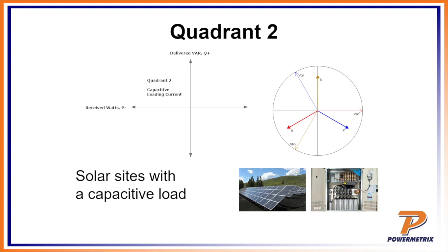So that power factor is going to shift a little bit, and it's going to shift as capacitive. This also could be representative if a capacitor bank is on the solar site, causing this artificial power factor. People have told me out in the field that they go to a site running load with a big capacitor bank still on, and it shows capacitance, which throws them off when they first see this.